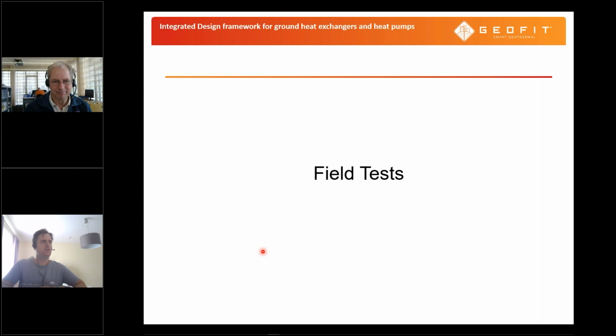Thank you, Michael. Yes, there is a question for you, Michael, from the audience, and they're asking your opinion about the use of propane in heat pumps. Propane as a natural refrigerant is already often used in heat pumps, but more or less in monoblock heat pump systems where the entire refrigeration circuit is outside. Yeah, so you have that for air source heat pumps. You have the heat pump outside, and you just go into the building with brine piping because of the flammability of propane.